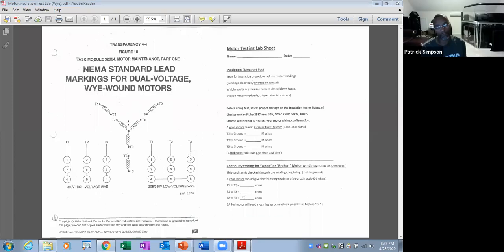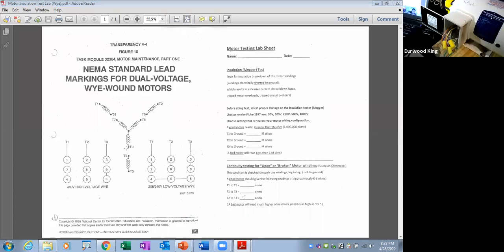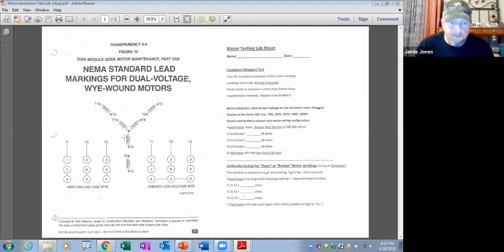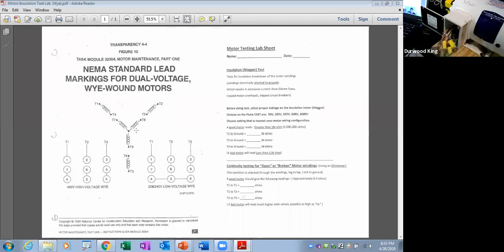Yeah. So a motor's either going to be Y wound internally or delta wound. And you're talking about the internal construction inside the motor that you can't see from the outside. So inside that motor, you have one winding here with 2 wires, another winding with 2 wires, another winding with 2 wires, and then you've got 3 sets of windings inside the motor that are a permanent Y. So here's what really makes it a Y, guys. This actually makes it a Y because these 3 are permanently wired together with a dot in the middle. And that's what makes it a Y wound motor, because you can't change that.